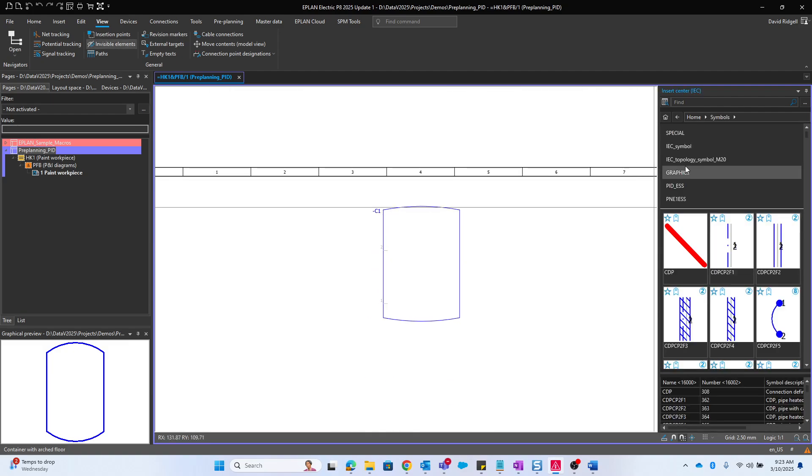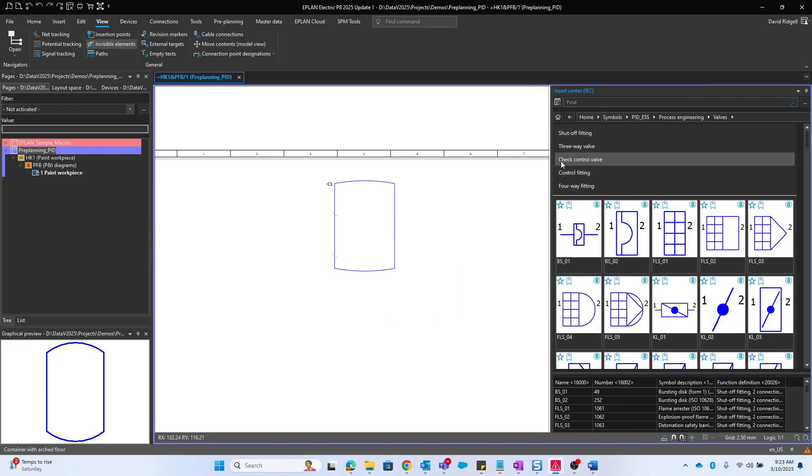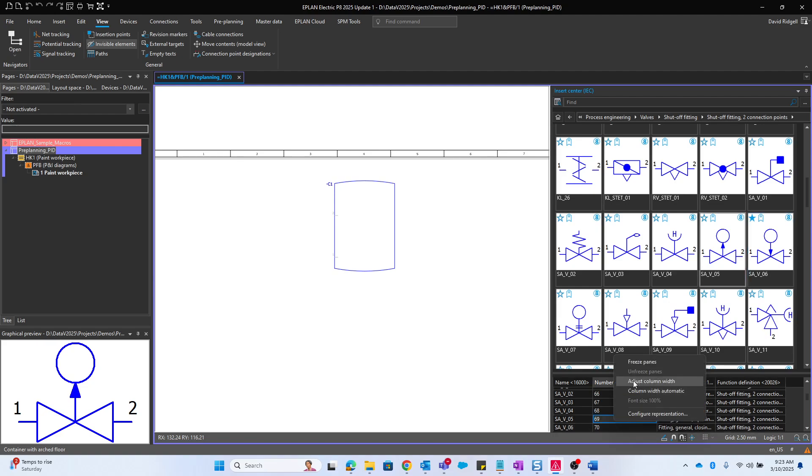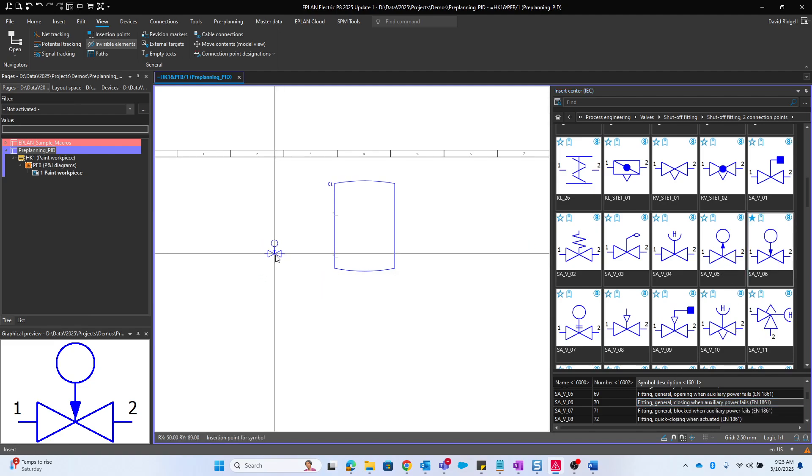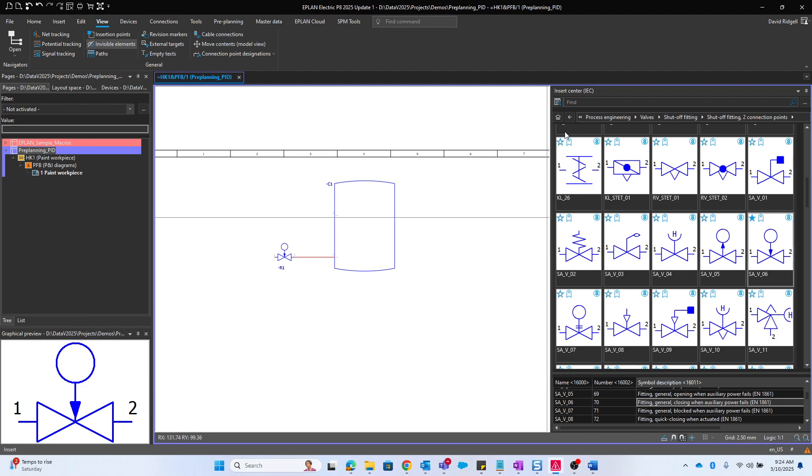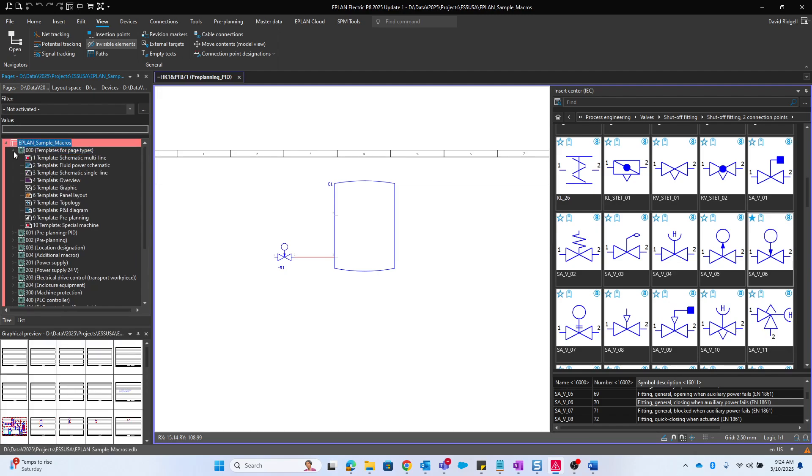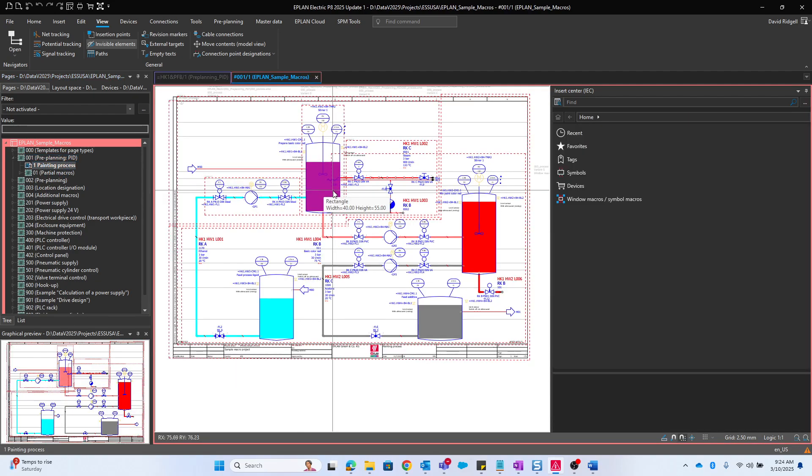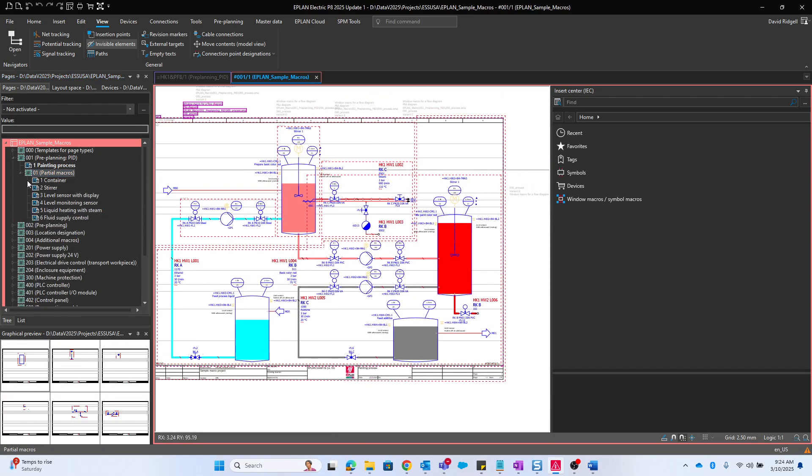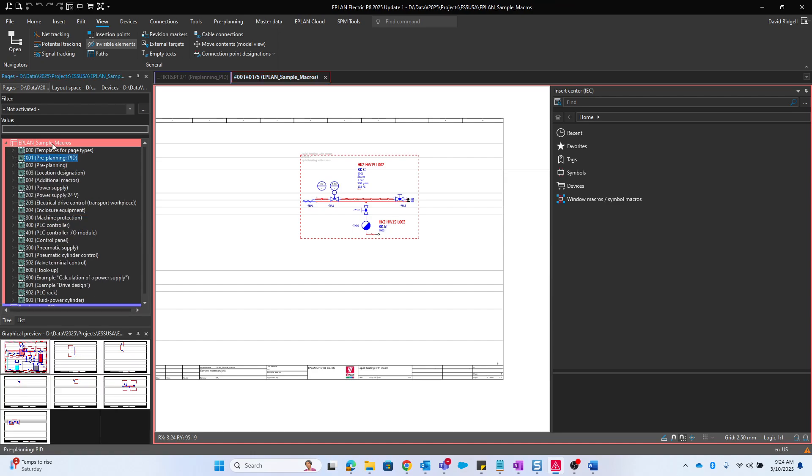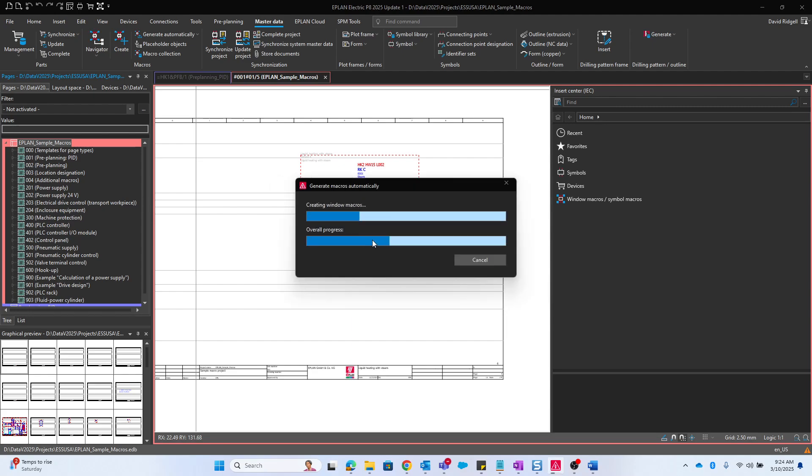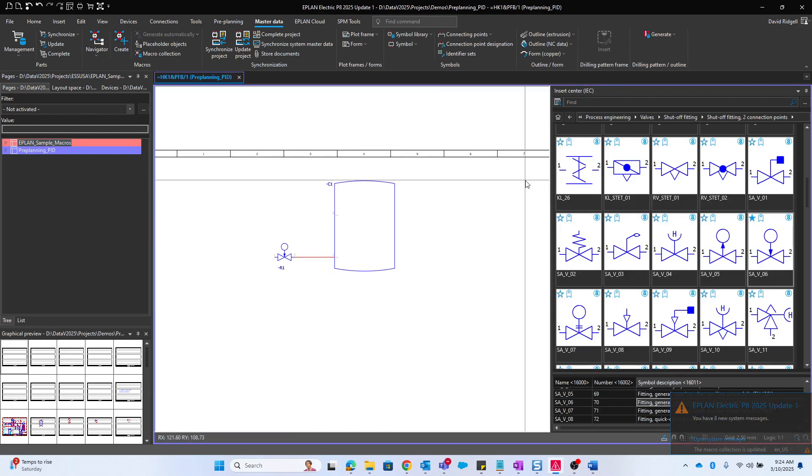In the insert center we can find our preplanning symbols under PID ESS process engineering. You can see all these different types of fittings and valves. The insert center tells us a description of what these are. For example, SA_V_06 fitting general closing power fails. Also in this ePlan sample macros project, which comes with every installation of ePlan, there are some standard P&ID macros that we can utilize. Different cutouts of a P&ID, different portions of it. I can utilize some of those by generating the macros and then they'll be available for me in the insert center.